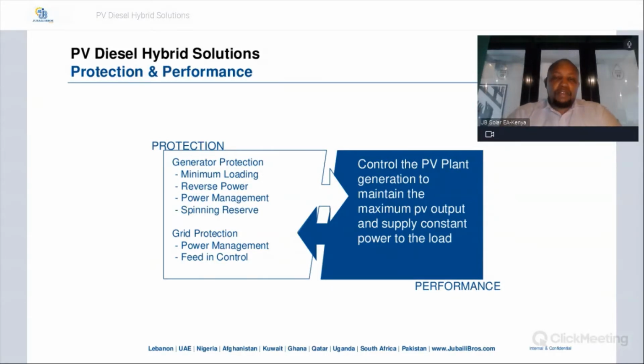So ideally, we have two functions. We have the protection function, where you want to protect the generator, you want to protect the load, and also protection from the grid, as well as performance. You want to make sure that your PV plant is operating at an optimal level and that you're maintaining maximum PV output and ensuring that you have a constant supply to the load. And we look at how each of these plays in the system.